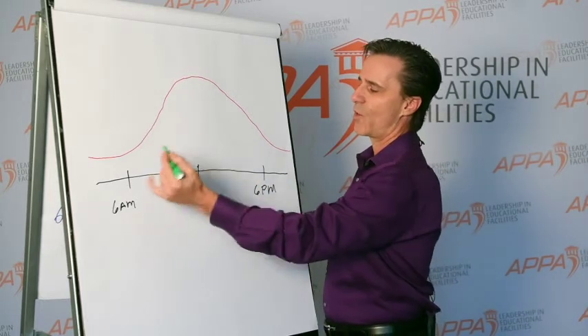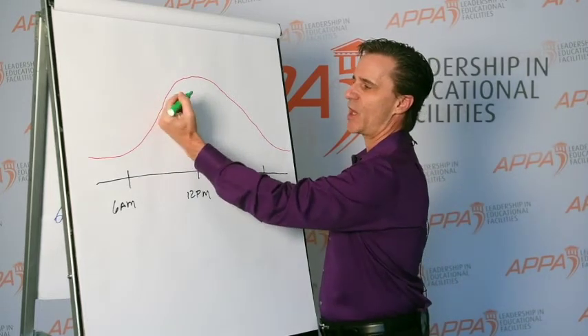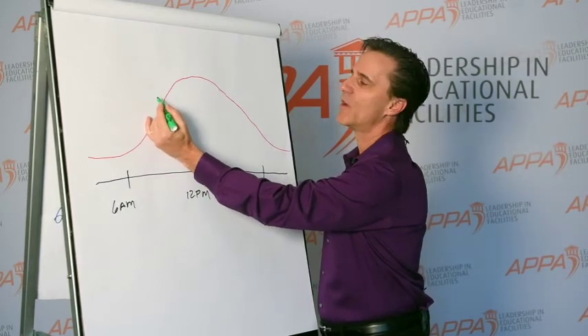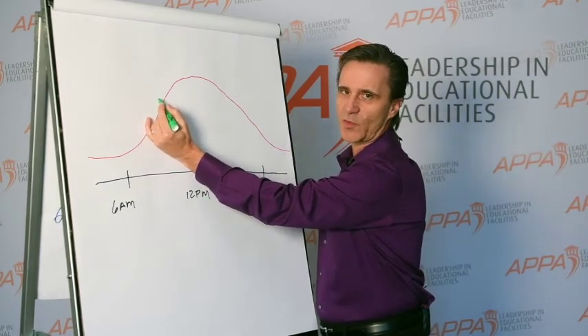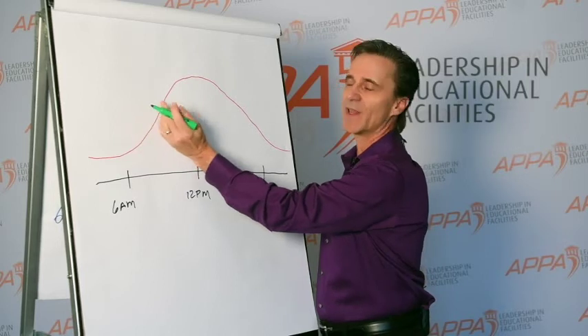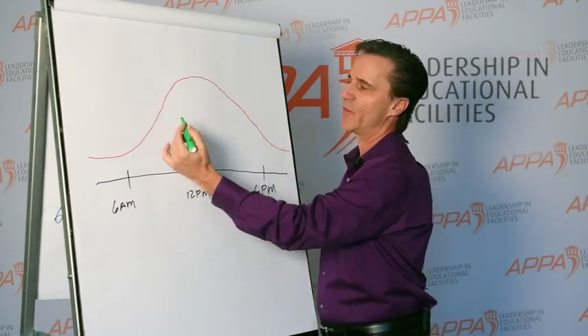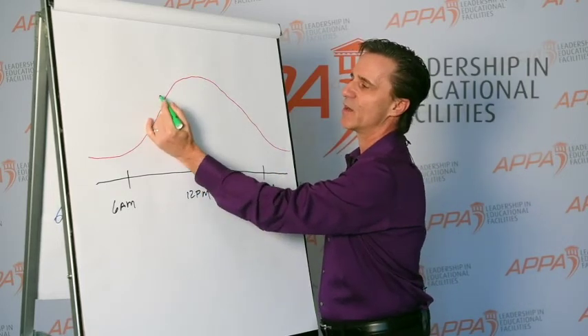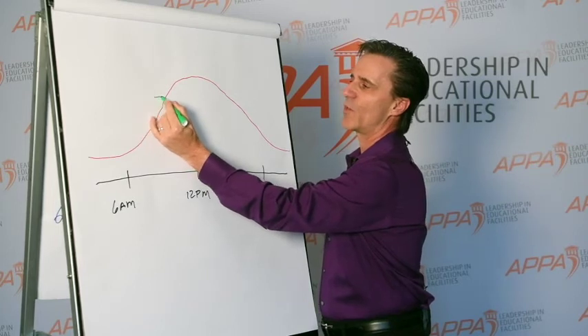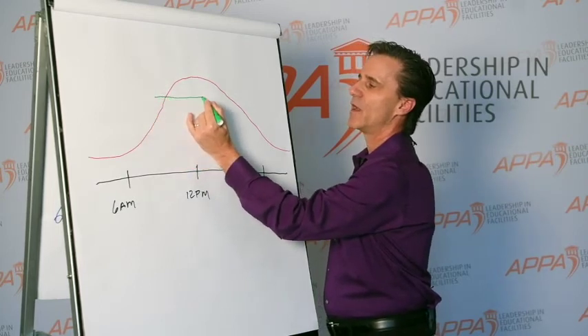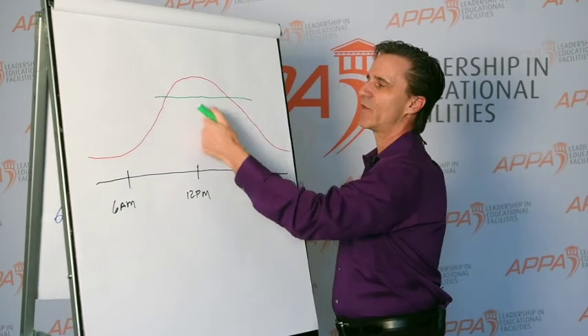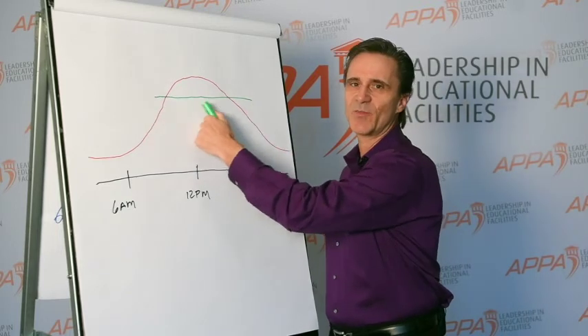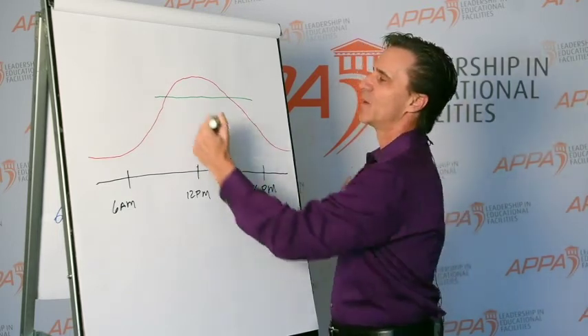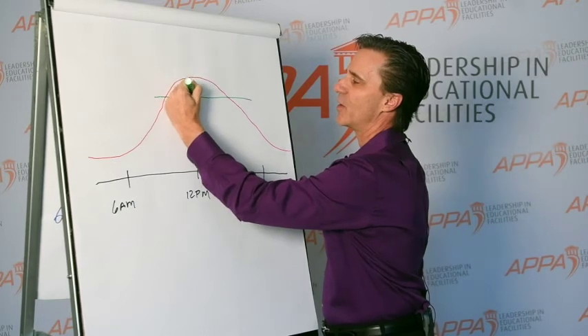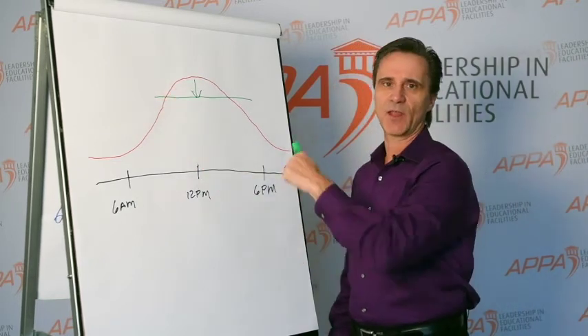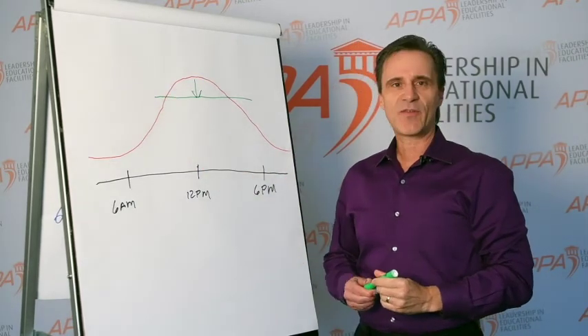So if we're approaching a peak period of time in the hot summer, we can start deploying our stored thermal energy, which allows us to start turning off some of our chillers. So instead of reaching a peak up here, we would deploy the stored thermal energy, turning off some chillers, and only consuming maybe this much electricity instead. This allows us to reduce our demand, flatten out that profile, and save a lot of money.